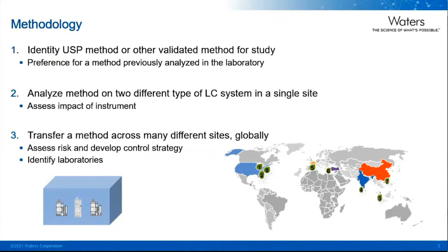We identified the USP monograph for quetiapine fumarate impurities as the method we would choose. The systems identified were the Alliance with an IEEE cable connection to the computer and a 2489 UV/Vis detector, as well as an ARC HPLC with a 2489 detector. Some of the key characteristics of the method include a high pH mobile phase at a pH of 9.2.